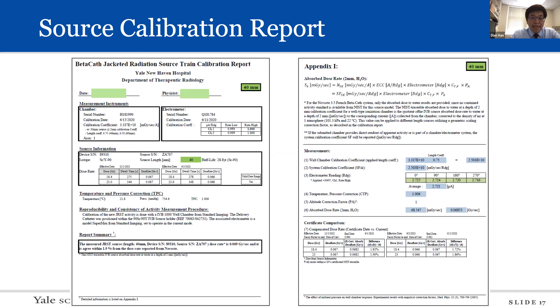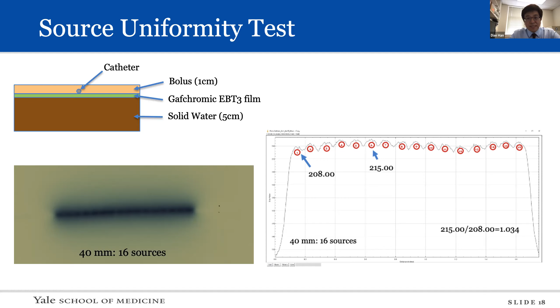And this is a uniformity test. We put the catheter on top of GafChromic film, put bolus on top for buildup, take the image and scan it, and then use analysis software to find the differences for the uniformity test. And this is an example of the daily QA report, which I mentioned in earlier slides. It includes the survey meter test, transfer device test, stopwatch functional test, documentation check, and emergency source recovery kit check.